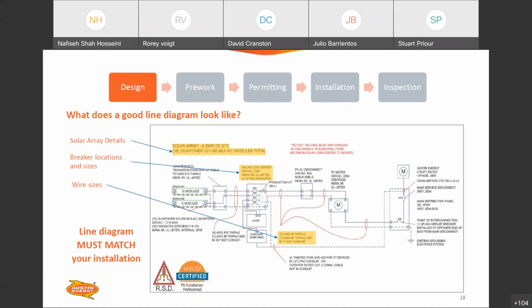And they've also noted that there's an existing grounding electrode system, which is not a given. So as far as designing the system from the beginning, this is something you should pay close attention to, because a designer will, by default, have that in their existing grounding electrode system, but you do indeed need to verify it during the site assessment. Alrighty, next slide.